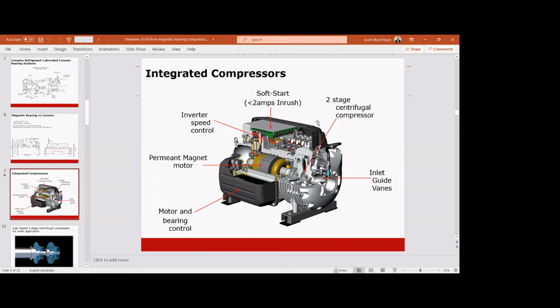In the top of the compressor is situated what we call the high power electronics, or the inverter. So in here we have what we call a soft start. We have silicon controlled rectifiers. We have an IGBT. So we go from AC coming in through a set of line reactors to reduce the harmonic. We come into the SCRs. We change from AC to DC. We put it through the IGBT, and then we come out as a high voltage AC chopped waveform to control the speed of the motor.